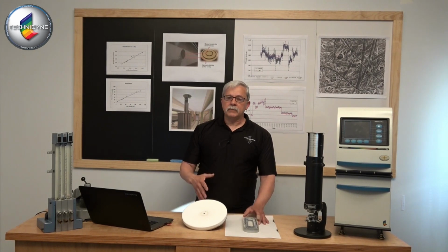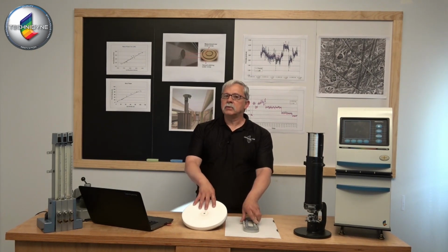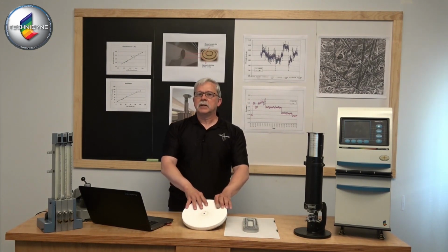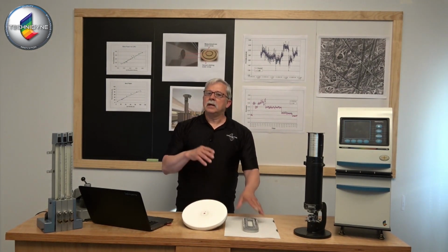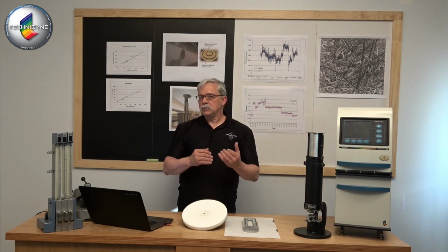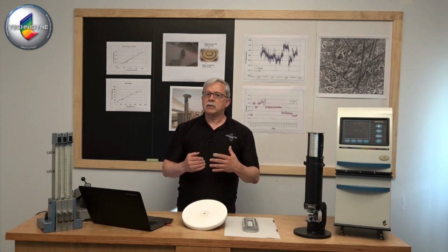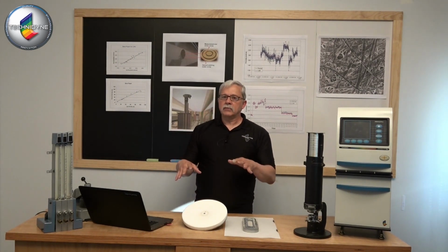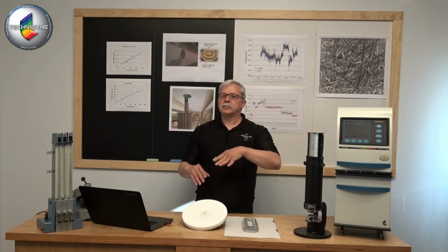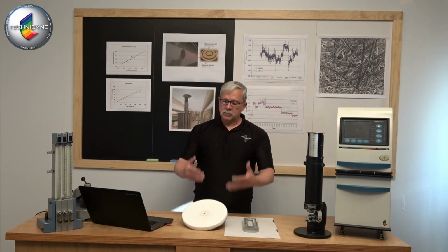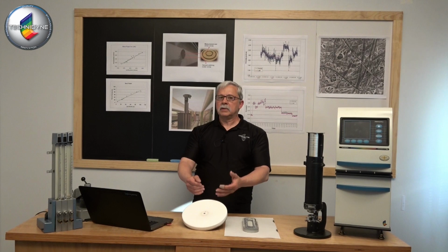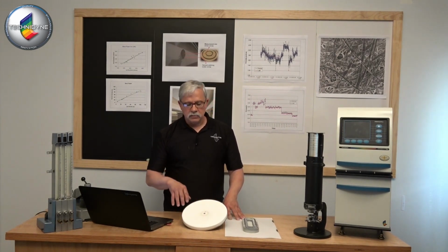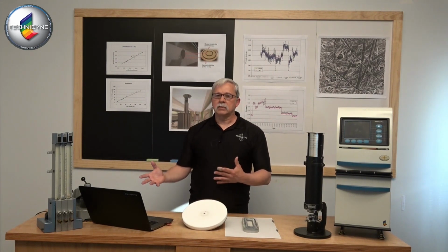Correlation work would be critical if you're looking at using this data to ship your paper by. But it's not imperative that you do the correlation. Really, what you need to do is establish the levels of measurement signal that you can get out of the system and use that in conjunction with whatever you're looking at in the laboratory, so that you establish that you've reached your level of porosity based on your laboratory equipment. Typically, the operator, the user of this equipment will in fact correlate to their benchtop equipment.